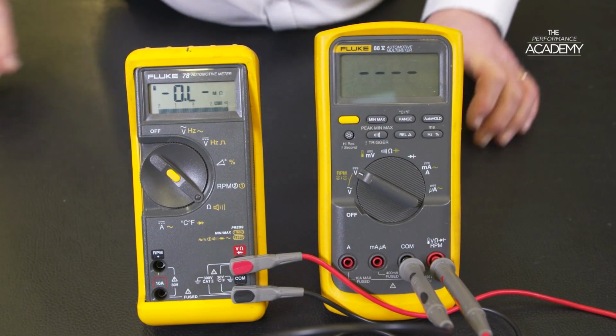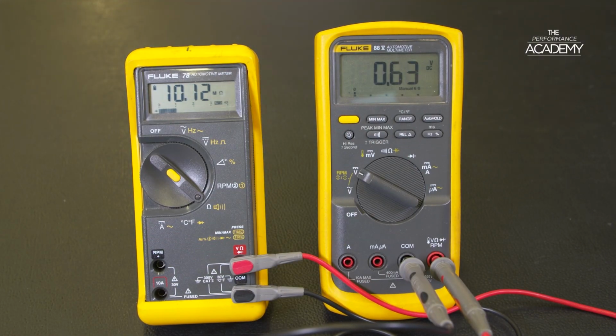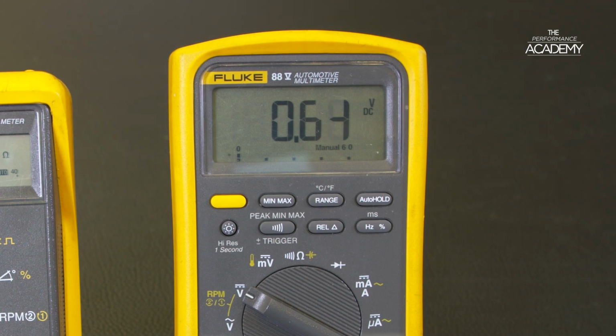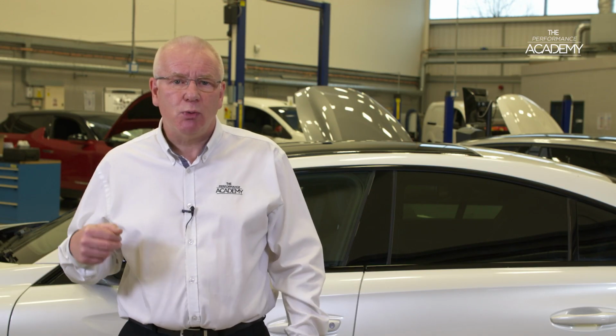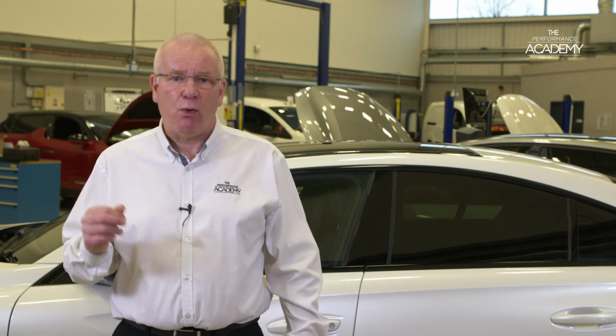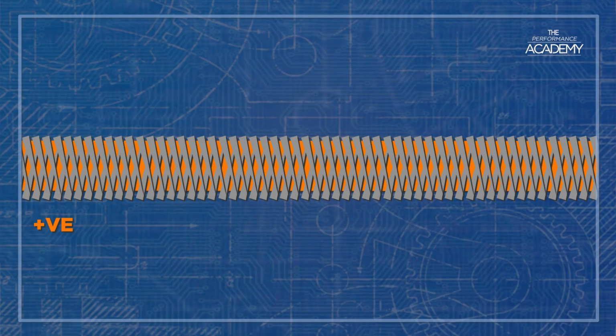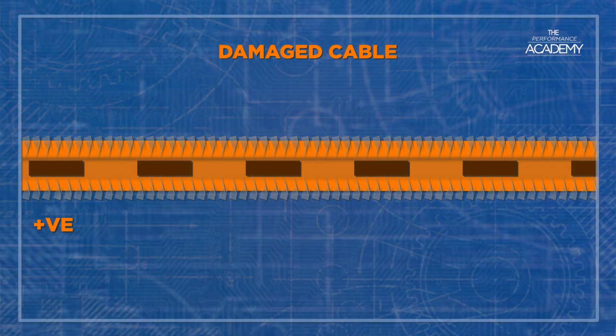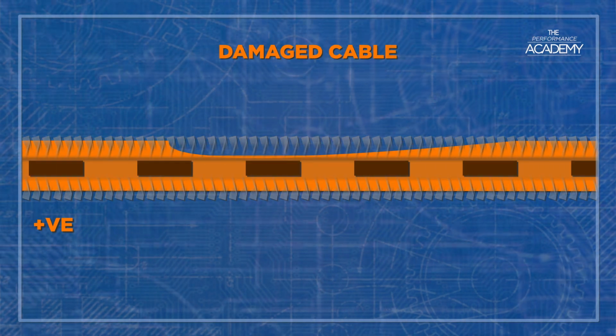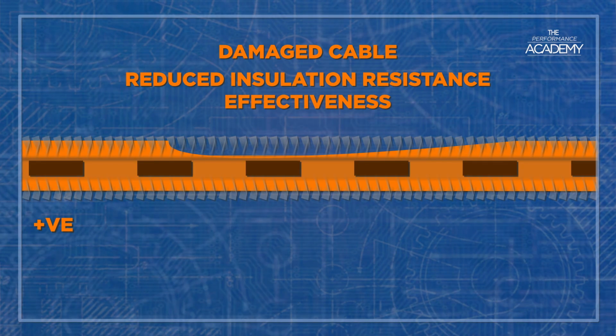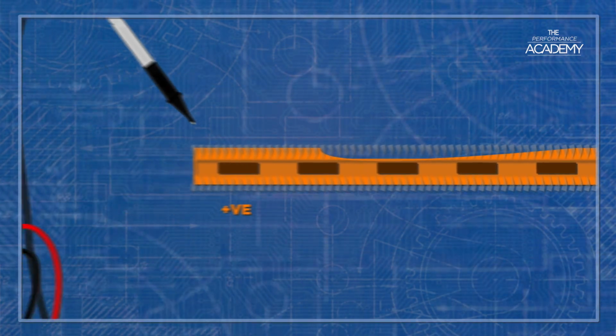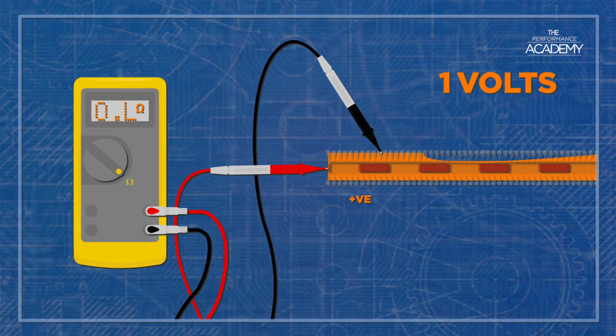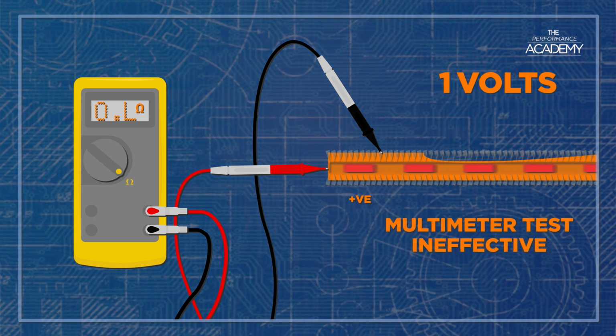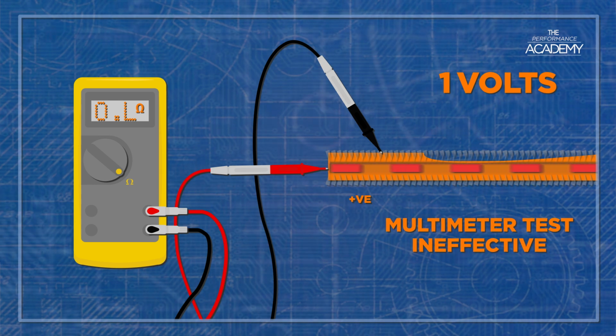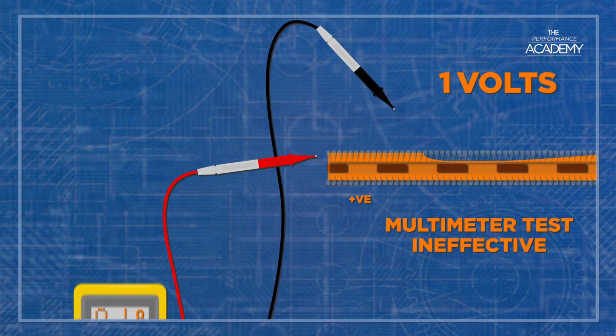This is due to the very low voltage they push out to do the test, usually around 1 volt. They do not have the voltage pressure to check if high voltage would push through the resistance at the contact point of a short. Remember, a short circuit resulting from damage to an electrical circuit or the breakdown of insulation rarely creates a perfect short. There's usually some electrical resistance within the point of contact creating the short circuit. However, when we're dealing with high voltages, the high voltage has the electrical pressure to easily push through quite high resistances, creating a short circuit to the supplementary insulating shielding or screening.